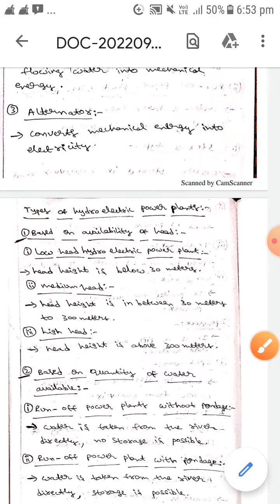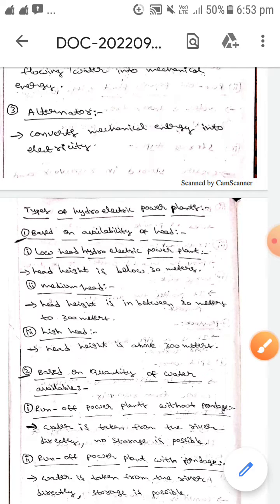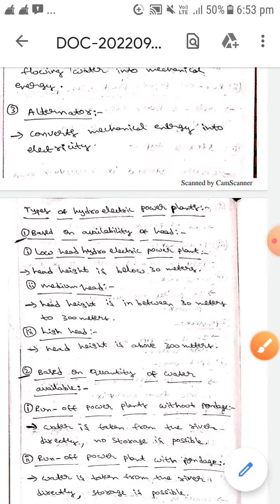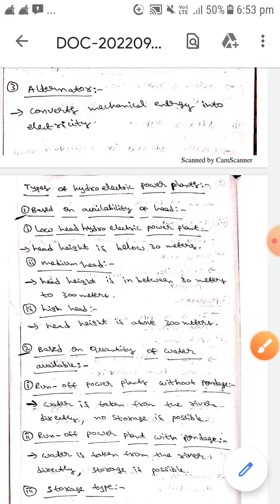The first classification is based on availability of head. Low head hydraulic power plants have a head height below 30 meters. Medium head plants have a head height between 30 to 300 meters. High head plants have a head height above 300 meters.